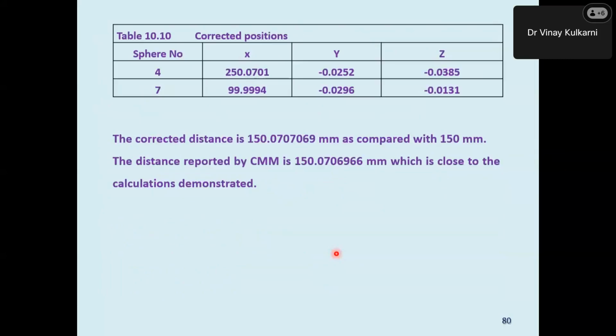Okay. So with this, we can say here that if, let's say, the sphere numbers 4 and 7, these are its optimum coordinates that we picked up. The corrected distance is 150.0707 as compared with 150 mm. So 150 mm was the nominal range here, and the distance reported by the CMM is 150.07. In fact, which is very close to the calculations demonstrated. So by using the calculations, I'm very proud to say that we have achieved 99.26%. In fact, very equivalent.